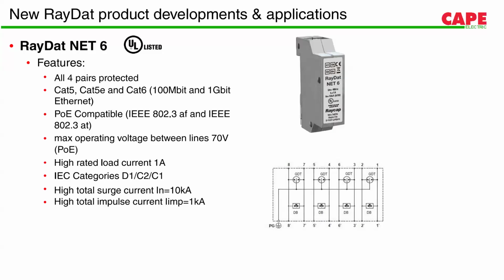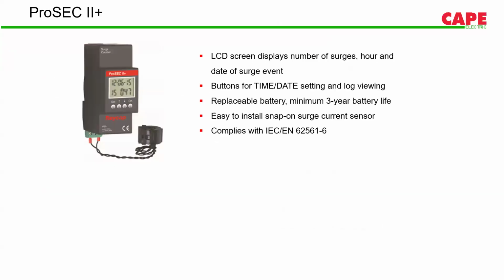for a communication system. And while selecting these Ethernet SPDs, you can see the internal diagram of this Ethernet SPD. We have provided four sets of protection components, four numbers of GDTs and diodes. Unfortunately, again in India, to reduce price, people will give one number of components and make it parallel across all the protection lines to reduce cost. But actually, it reduces the reliability and efficiency of an SPD.